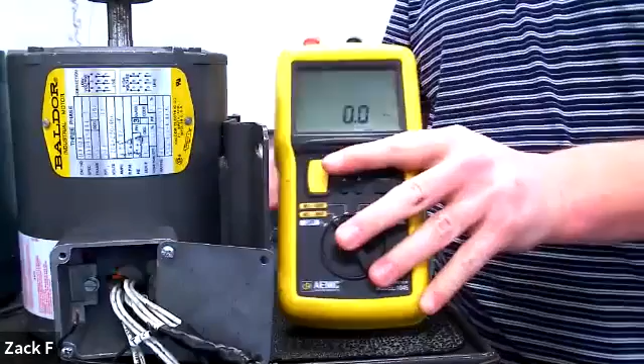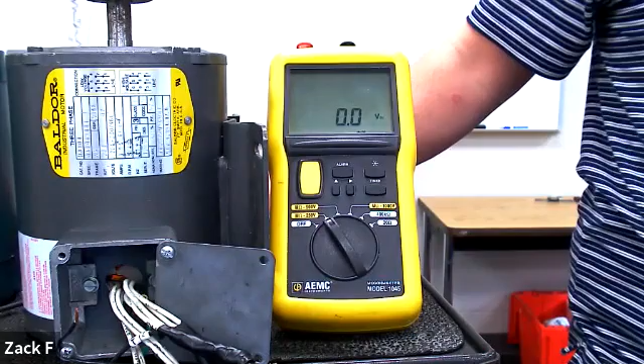So I kind of smushed that down into that screw, and this ground is made up to the casing. I'm going to try to see if I get a reading now. So back to the definition of integrity and what a megger does. Think of it like the water pipe analogy, right? Electron flow, current flow is like water in a pipe. A bigger voltage is like having a bigger pump or bigger pressure, bigger force on that water. And current is the amount of water passing through one point in a given amount of time. Resistance would be whatever's resisting that current flow.